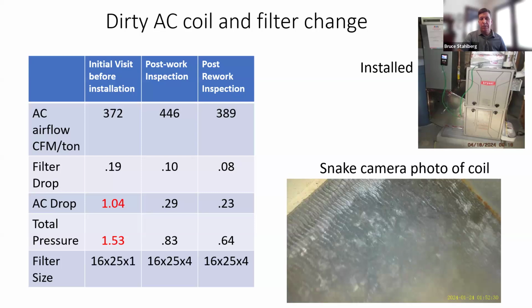And we did a test. Our airflow came in a little bit high at 446, but you can see the AC drop was way better at 0.29. So that told me that they did get in there and actually clean the coil. So I tweaked the furnace, slowed down the blower motor a little bit more, and we came in at 389. And this is actually really good numbers. Notice that the pressure is more than 0.5 at 0.64, but I can totally live with that. And I feel like this system is going to work much better.